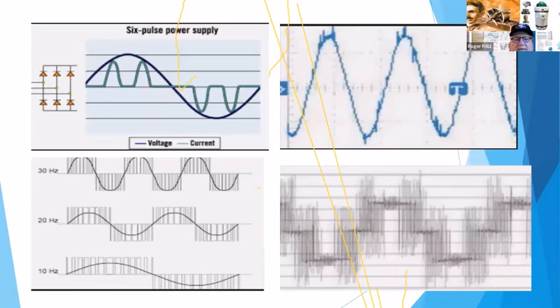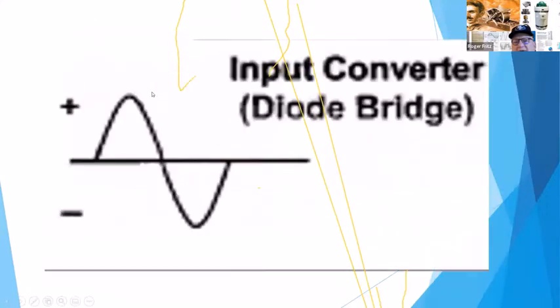Some areas that I did want to bring up that are crucial when you're building these kind of application systems is to understand that the output waveform is not sinusoidal, as it shows down here on the right. It's this PWM, that we're basically doing the same thing that they do in radios and in frequency controllers and those things. So this is the voltage, the black here, and this is the actual current draw from these diodes triggering back and forth dependent on the load inside the drive circuit.